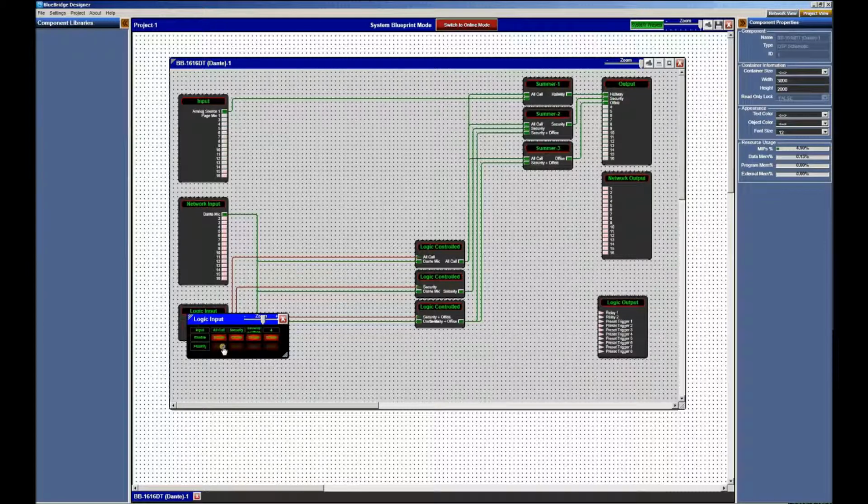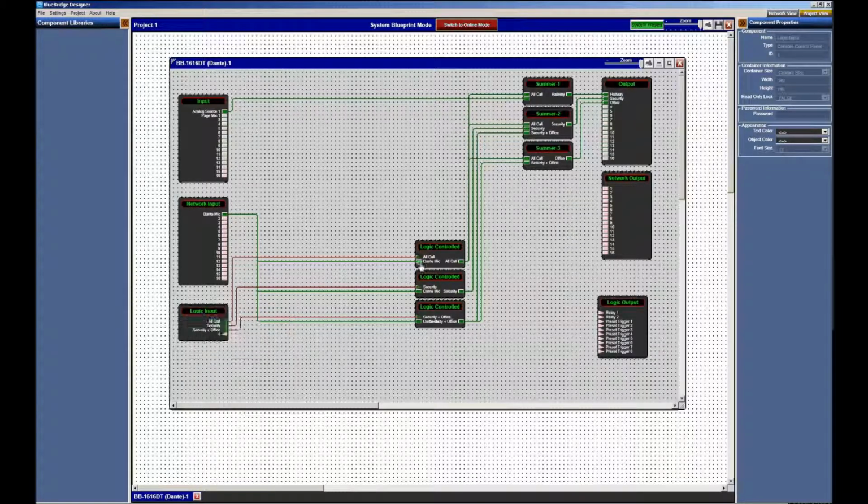This way, whenever a logic input is triggered by an outside source, you can go ahead and have that mute or unmute these things. If behavior is opposite of what you had wanted, if it, for example, is not continuously muted and only mutes when a trigger is pushed, you may just have to invert that here.